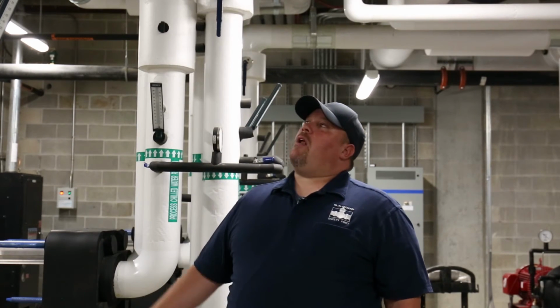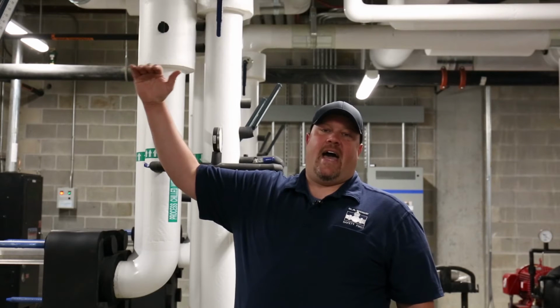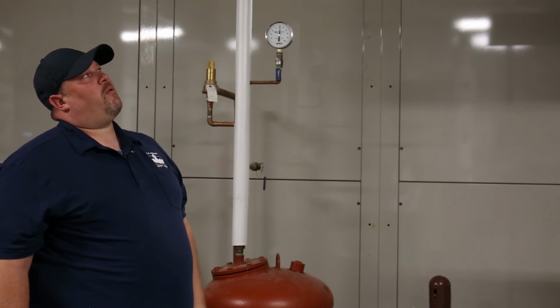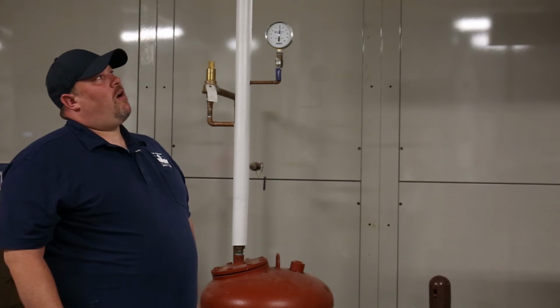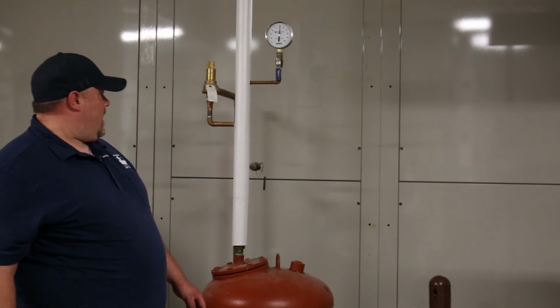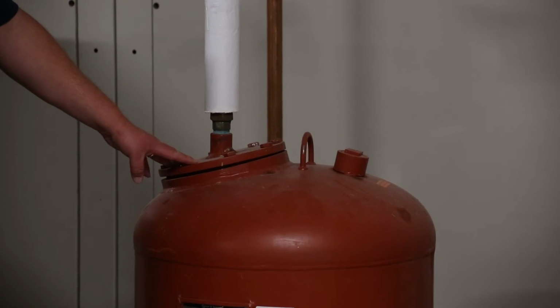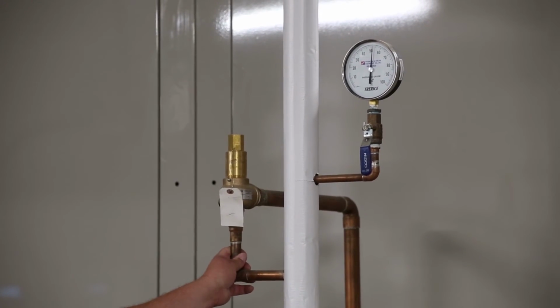All of the pump flows are balanced by the variable frequency drives. The automatic flow control valves are to limit the maximum that can be circulated through the system. Typical with every closed system loop in the building, like here we have our process chilled water, we have our air and dirt separator that has an automatic air vent off the top, as well as the makeup water feed preset to each system. That also has an expansion tank tied in with its own automatic air vent, pressure gauges, and relief valves for each individual system.